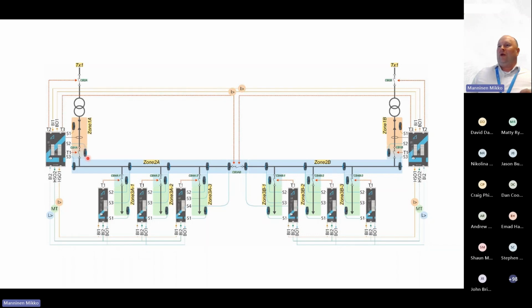This is now just one example with the relays and the point sensors. The point sensors are typically monitoring, for example in medium voltage, every closed compartment, which means that typically there is one sensor for the bus bar, one sensor for the circuit breaker, and one sensor for the cable termination, or any closed compartment. If it's metal-enclosed switchgear, then you do not need to have a point sensor in each cubicle if the bus bar section is fully open. So one in every second compartment is fully fine, because if there's an arc flash in the bus bar compartment, it will travel hundreds of kilometers per hour to the end of the bus bar and through the wall.